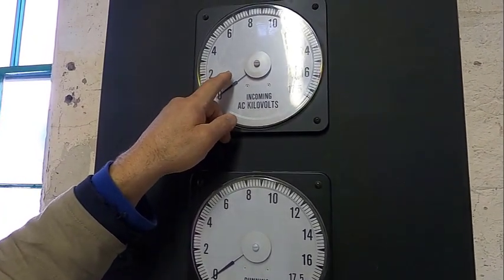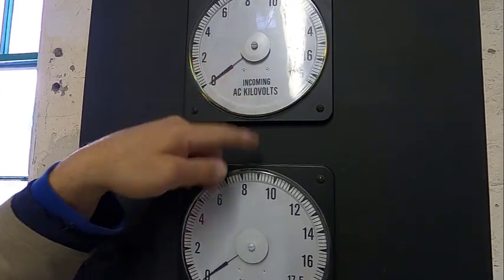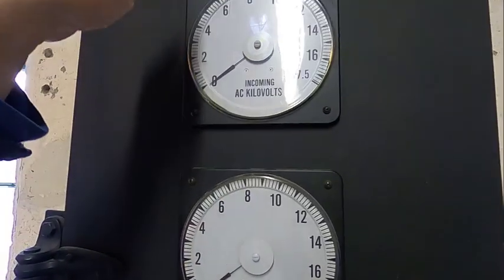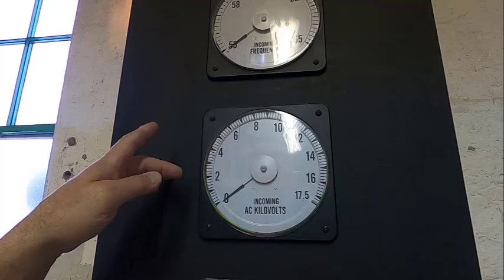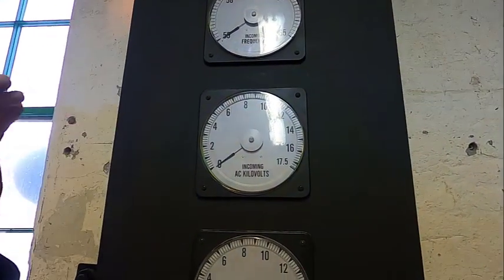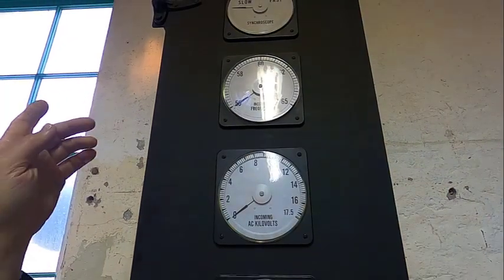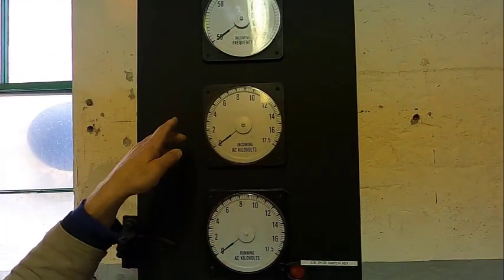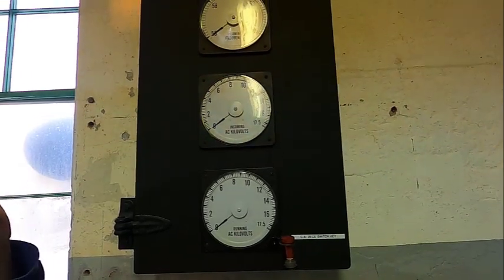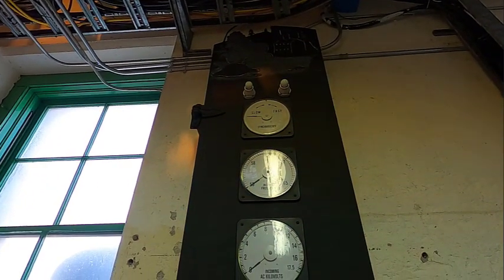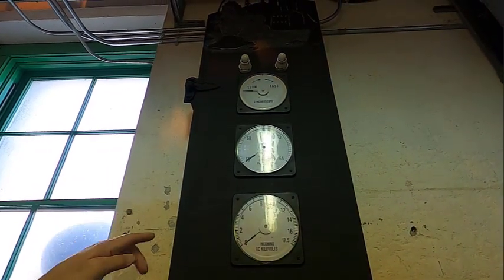So these voltmeters have to match, so it's adjusting the excitation voltage on the unit that's incoming to match the running, match the grid, and then that's the frequency. So that frequency is basically telling you the speed of the unit. When it's correct, it will give you that 60 hertz, which is the 12 o'clock position. And the synchro-scope, the top guy, is actually telling you the frequency, whether the unit's going too fast or too slow. It's just confirmation of the frequency in a sense. And the two light bulbs are telling you again the voltage difference between the grid, the load, and the unit. So when the light bulbs go out, that is the actual signal of when it's safe to close in the breaker. Oh, very cool.